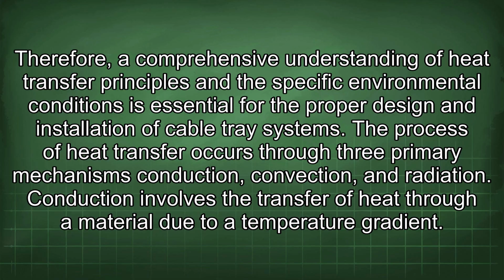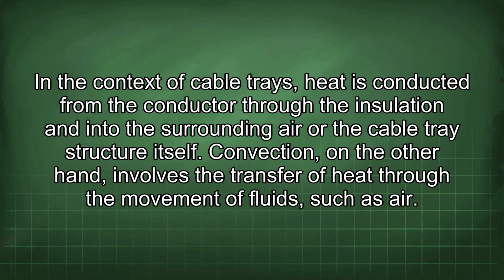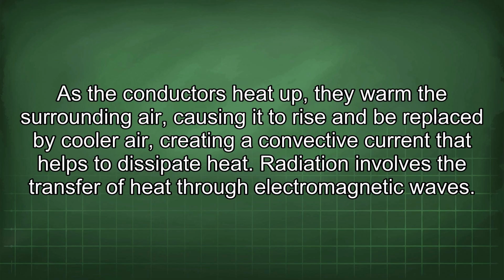The process of heat transfer occurs through three primary mechanisms: conduction, convection, and radiation. Conduction involves the transfer of heat through a material due to a temperature gradient. In the context of cable trays, heat is conducted from the conductor through the insulation and into the surrounding air or the cable tray structure itself. Convection, on the other hand, involves the transfer of heat through the movement of fluids, such as air. As the conductors heat up, they warm the surrounding air, causing it to rise and be replaced by cooler air, creating a convective current that helps to dissipate heat.